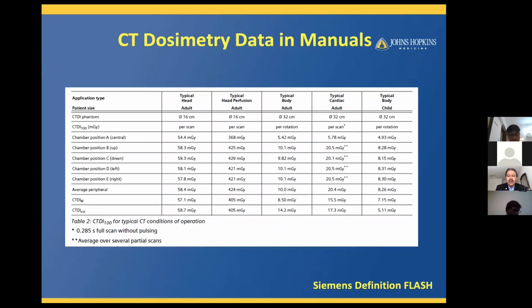For a medical physicist working in a clinic, one of the important roles is acceptance testing. When a new scanner arrives, we do a lot of acceptance testing to verify whether the scanner output is as it's supposed to be. For that, we can take advantage of the technical specification of the manufacturer, because manufacturers provide these types of dose tables, which they have done in the factory, and which display the dose for different locations and different compositions. One of the primary aspects of a medical physicist is to mimic this measurement and make sure the techniques are similar to what they are getting. That will tell you the scanner output is the same as indicated.